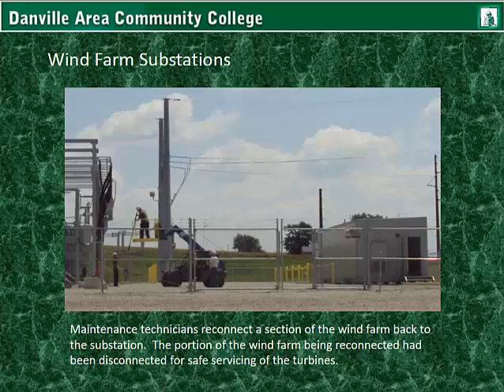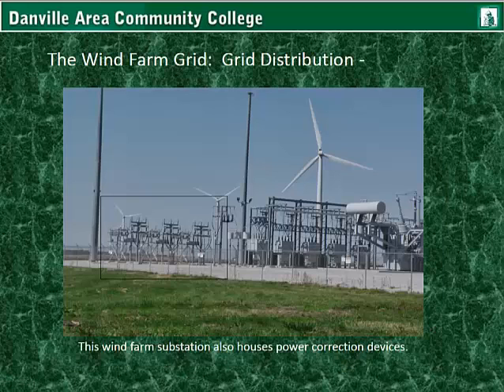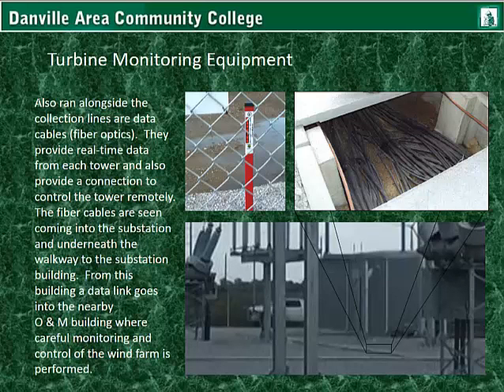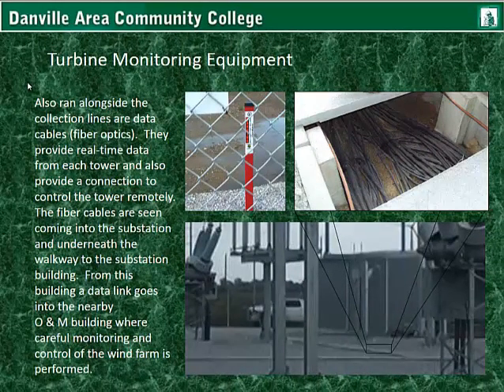Maintenance technicians reconnect a section of the wind farm back to the substation — the portion had been disconnected for safe servicing of the turbines. This wind farm substation also houses power correction devices. Also run alongside the collection lines are fiber optic data cables. They provide real-time data from each tower and also provide a connection to control the tower remotely. The fiber cables come into the substation and underneath the walkway to the substation building, where a data link goes into the nearby operations and maintenance building for careful monitoring and control of the wind farm.